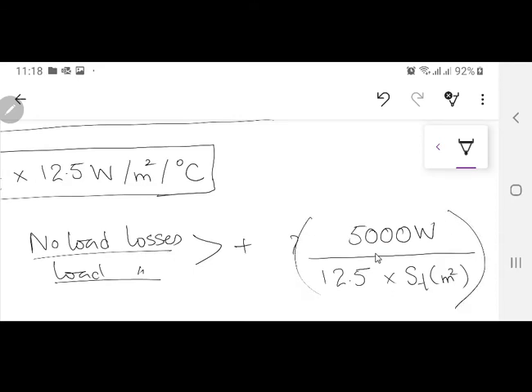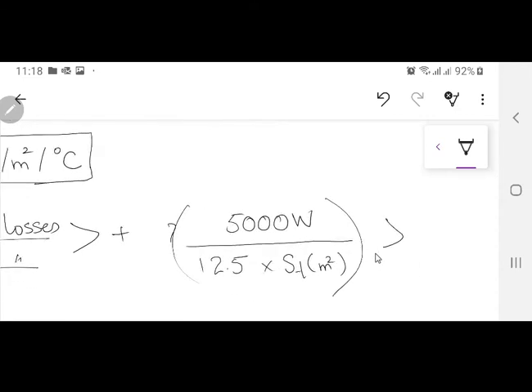If this value comes out equal to 40 degrees centigrade, this means you don't need anything else, the tank is sufficient. But if you get something greater than your required degree centigrade value, this means you have to put some additional radiator on the tank so that it can be cooled down.